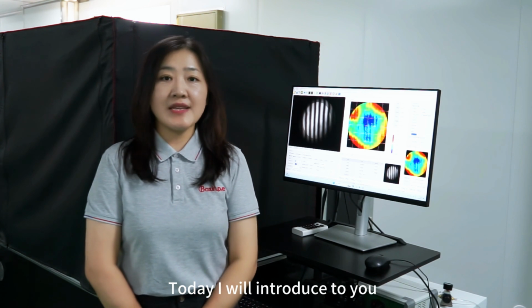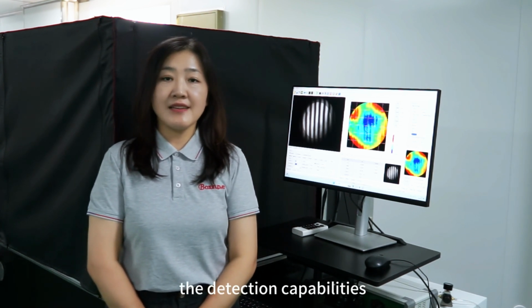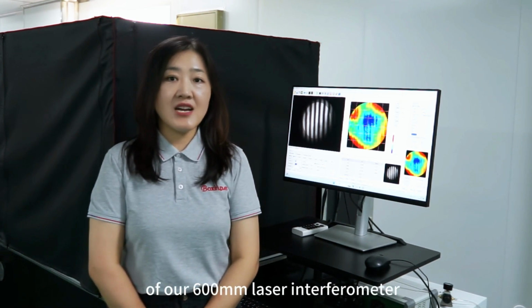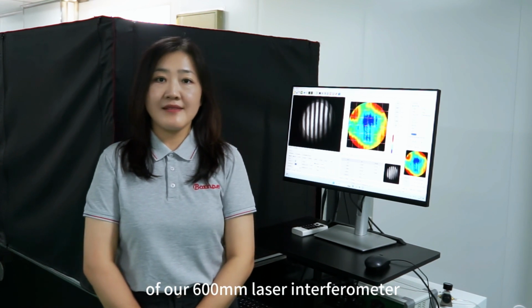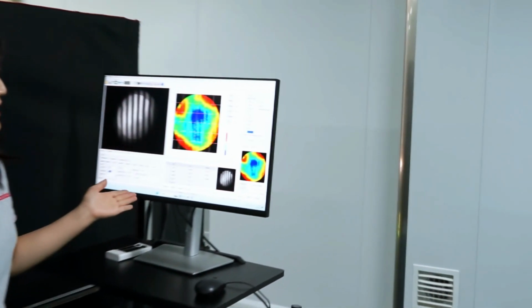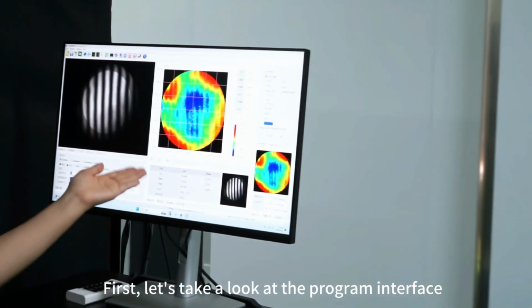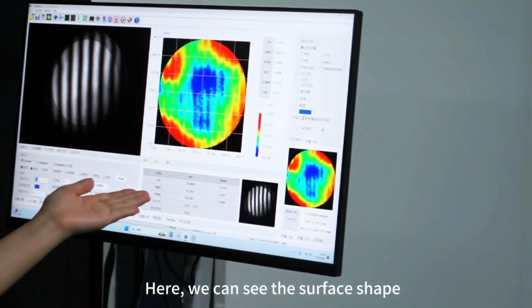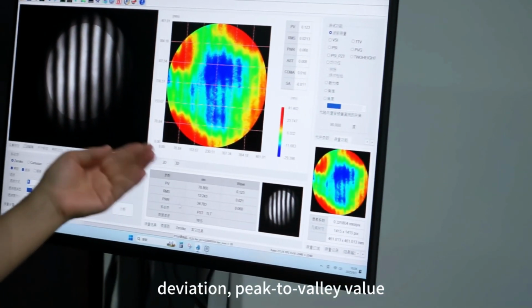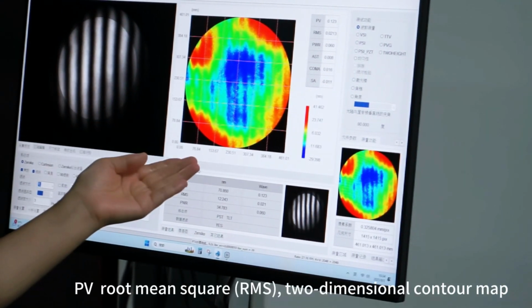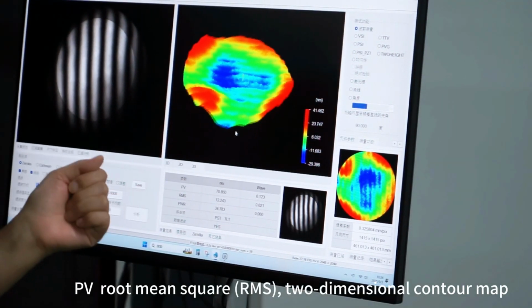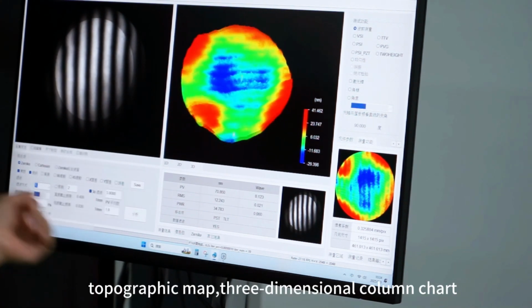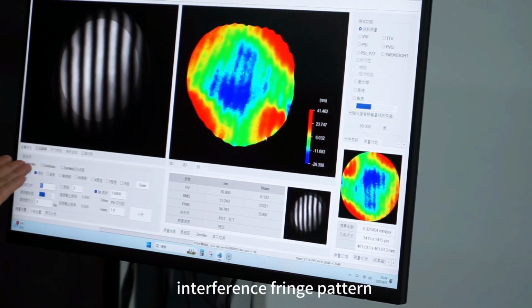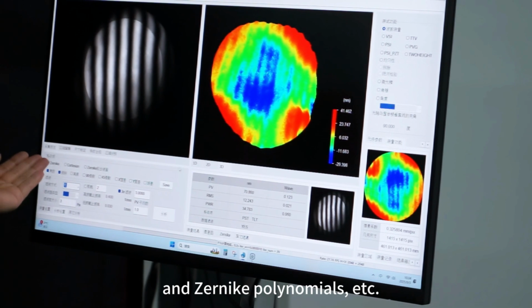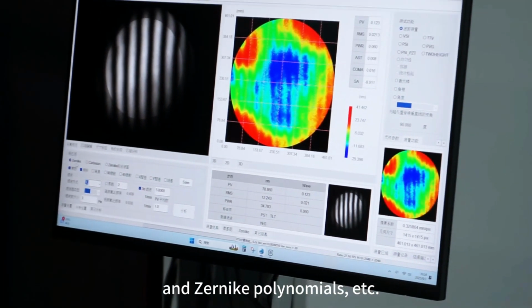Today I will introduce to you the detection capabilities of our 600mm laser interferometer. First, let's take a look at the program interface. Here we can see the surface shape, deviation, peak to valley value, PV, root mean square, RMS, 2-dimensional contour map, topographic map, 3-dimensional column chart, interference fringe pattern, and Zernike polynomials, etc.